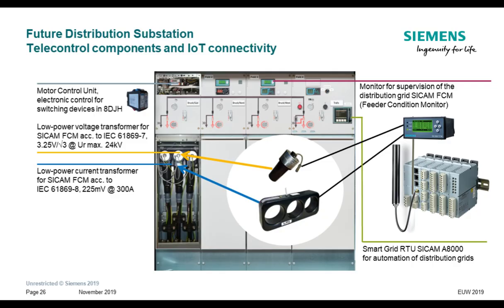Going further to the real hardware which is needed for this kind of installation, as Bernd also explained about the Blue GIS, our medium voltage switchgear, I would like to dive a little more into the configuration of the medium voltage switchgear itself. Bernd also mentioned the sensors, but in this picture we can really see the sensors: the voltage sensors, the voltage dividers, including the temperature sensors, and also the current sensor, which can be directly integrated in the medium voltage switchgear. What is also quite important is that we are using low power voltage transformers and low power current transformers, sensors fulfilling the standard IEC 61869, for example /7 and /8.